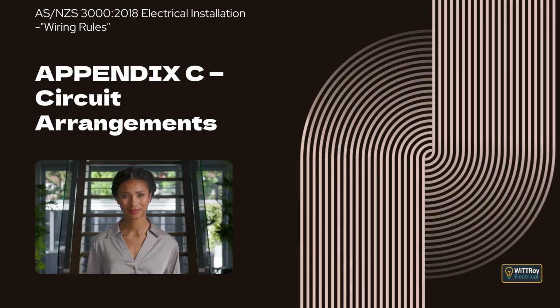This clause explains that maximum demand in final subcircuits is determined differently from consumer mains and submains. For a single item of equipment, the demand is based on the connected load. For multiple items of equipment, the demand may be limited by the rating of the circuit breaker protecting the subcircuit.